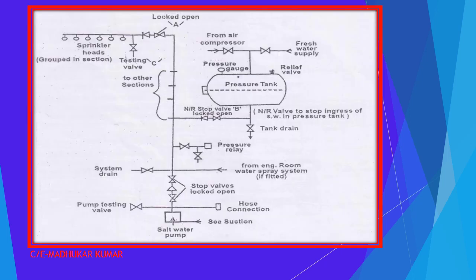Okay, here we are going to see the basic working principle of the complete sprinkler system, with the help of this diagram explanation. So here you can see this is your pressurized tank, and we have fresh water installed in that, and the compressed air which is coming from here, and if the water reduces, the fresh water supply is also there. The pressure gauge we can see over here, and the relief valve is also seen over here. Okay, you can see that this is the non-return stop valve B, which is locked open, and in this section, let's suppose we talk about this section, this is valve A, which is also locked open.